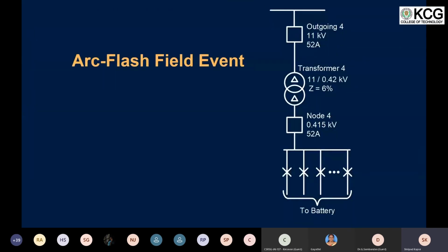Just to explain in addition, there are multiple sets of batteries that are connected onto a common node, and you have four such nodes. In each node, the total capacity is about 2.5 megawatt in this particular installation. And then you have the step up transformer, which is again connected to the 11 kV switchboard.